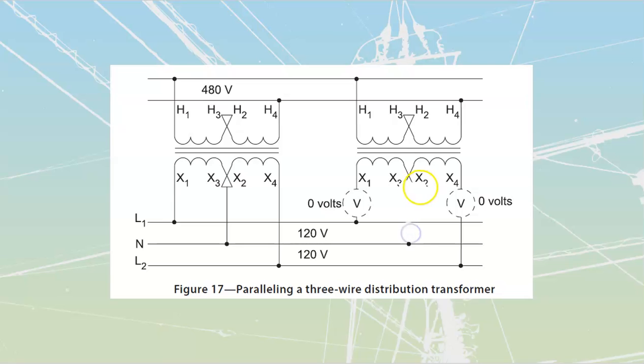Because where this gets a little bit more confusing is when we have a transformer that doesn't have all the same terminals. Like over here, we've got this, X1 and 2 to 3 to 4 like that. But in some cases, we might just have a transformer that looks like this, where it's got an X0, and this one here has got an X2 that is going to be off of it. In that case, same deal. We're going to connect our neutral in to the same point that we have our neutral over here. This is a split winding. This is one that's got a manufactured neutral inside of it.